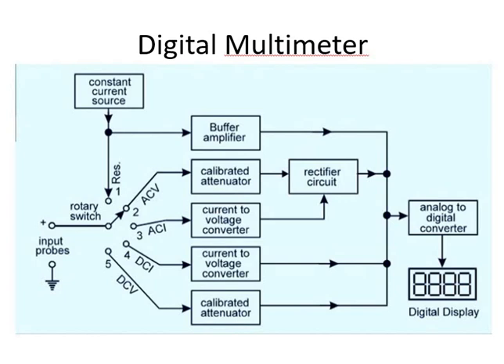When the rotary switch is at position 1, it is known for measurement of resistance. The resistance is connected to the input probes and the constant current source drives a current through the unknown resistance. This produces a voltage across the resistance directly proportional to the resistance. It is given to the buffer amplifier and then to the analog-to-digital converter. The ADC converts it into an equivalent digital signal, which is displayed on the digital display.